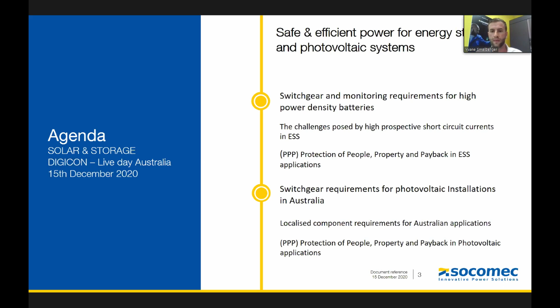So this goes into detail about the challenges posed by high prospective short circuit currents in ESS. Addressing something that I like to refer to as PPP, which is the protection of people, property, and payback. And then moving into a second level, which is switchgear requirements for photovoltaic installations that are specific to the Australian market. So here, touching on localized component requirements for Australian applications. And again, looking at the PPP, which is protecting our people, our property, and the payback of our system.